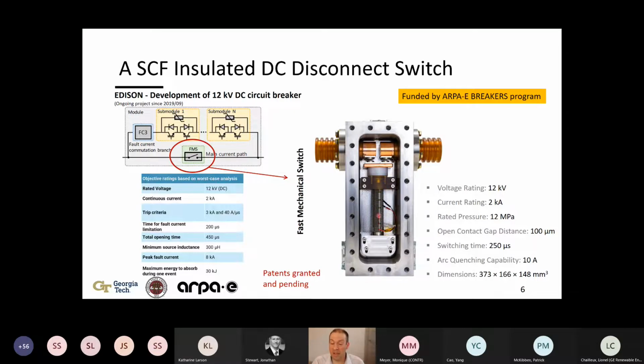And it uses a piezoelectric actuator to move the contacts extremely fast. It doesn't move them very far, we are talking about a 100 micrometer displacement, but it does so very fast, switching time around 250 microseconds.